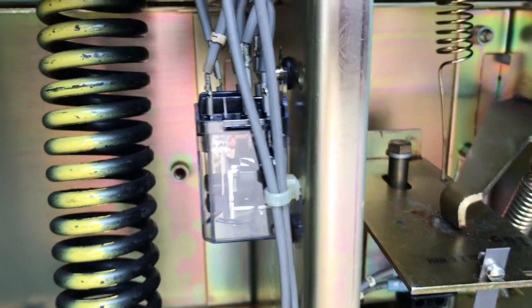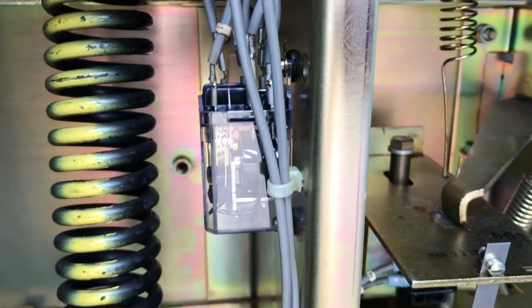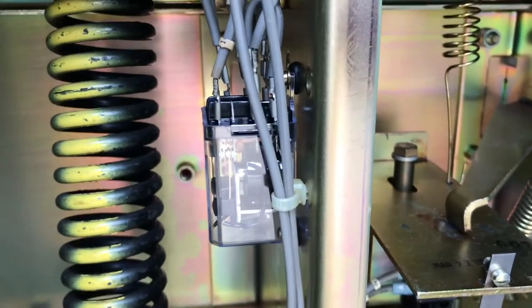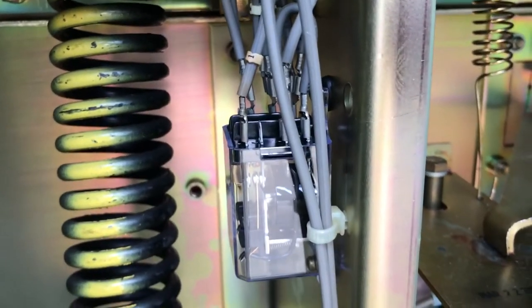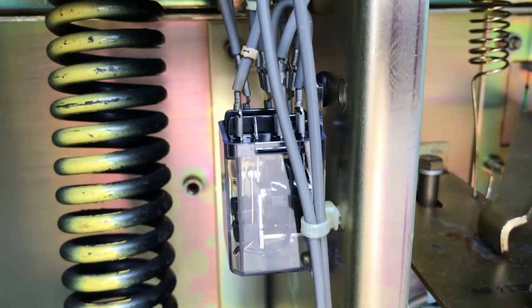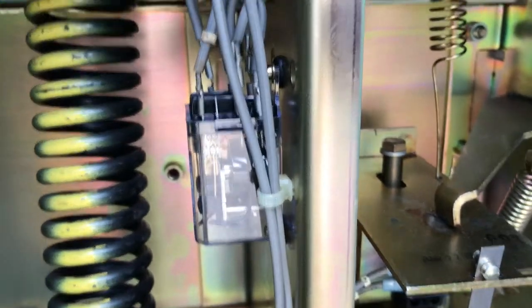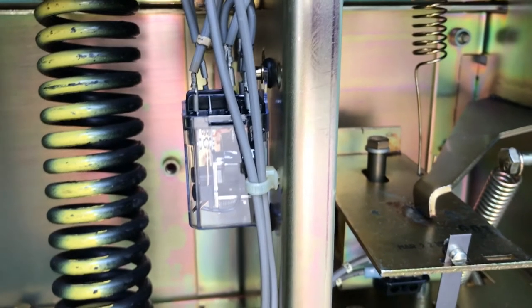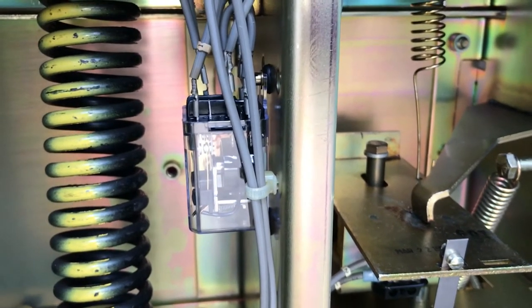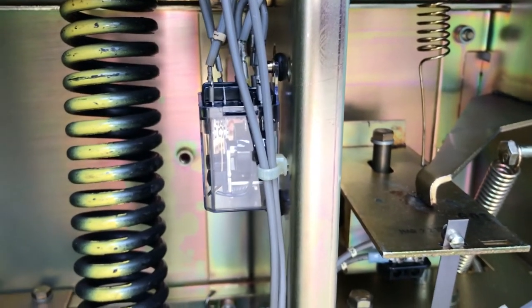My hand is still on the closed switch, so that anti-pump relay is still energized. But it's doing exactly what it's supposed to do—it's not trying to close the breaker again.